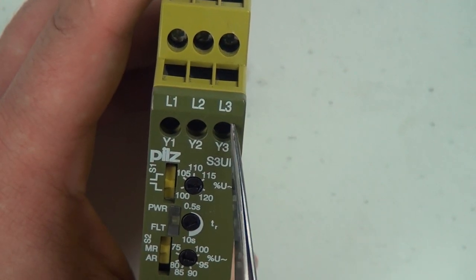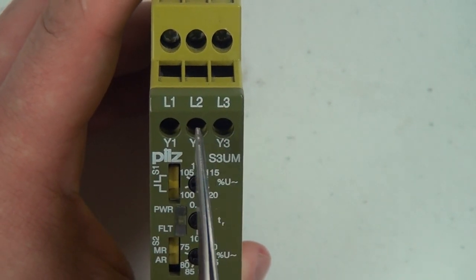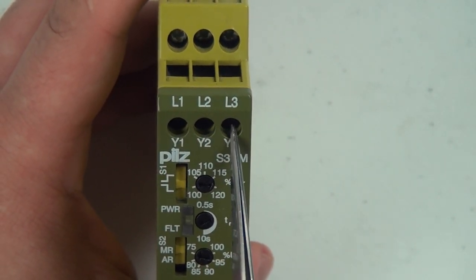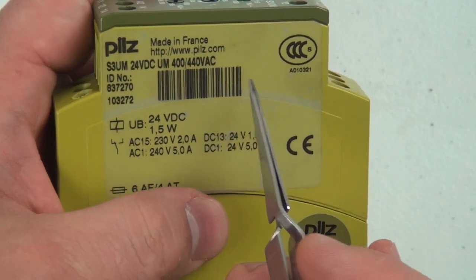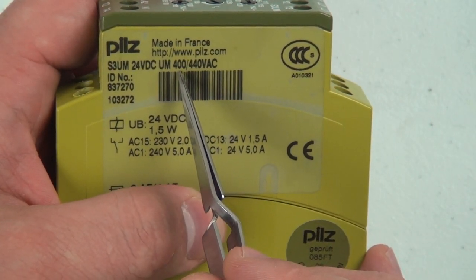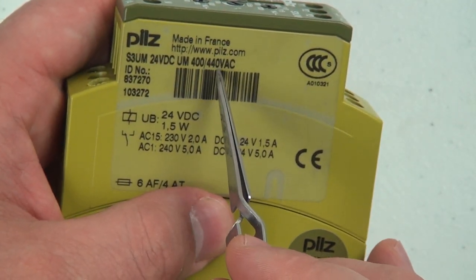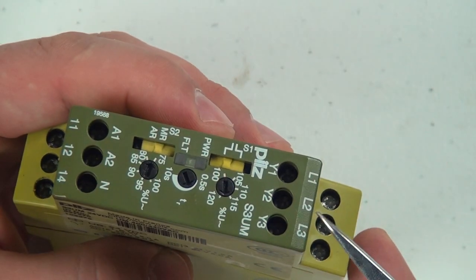Now, if you tie Y3 to Y2, this gives the thing a little bit more headroom. So normally it's 400 volts, but if you tie Y2 and Y3 together, now it becomes 440 volts. And that's the only reason there.